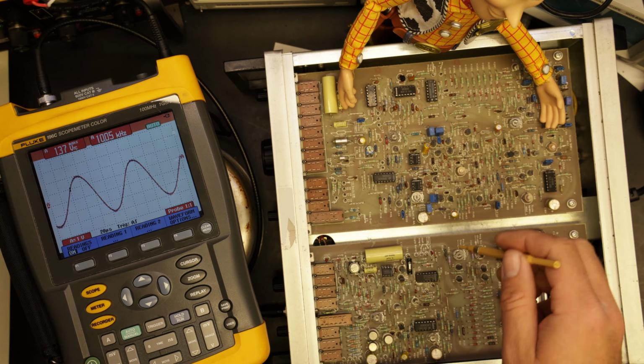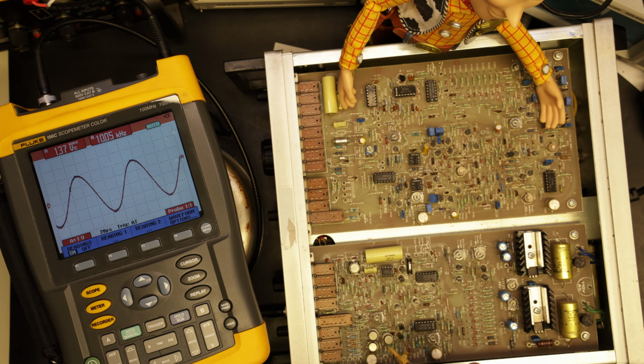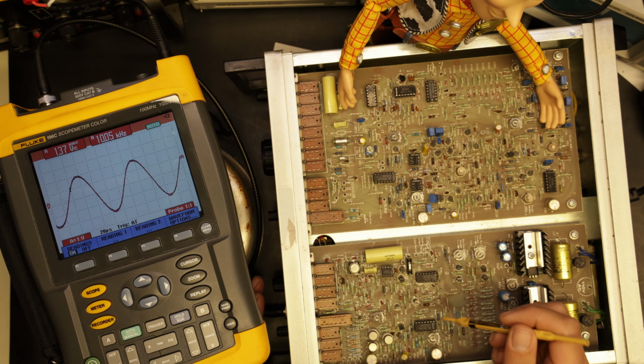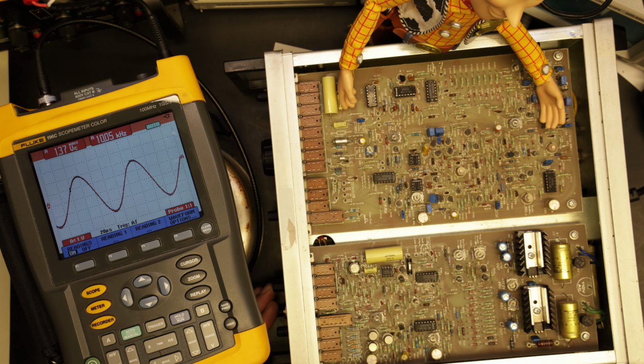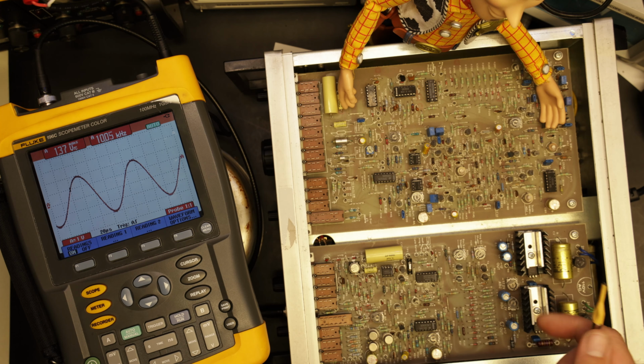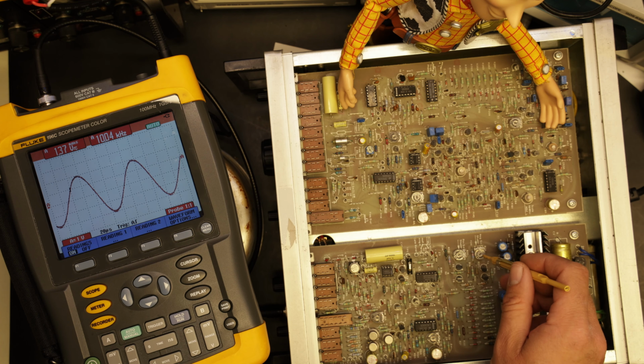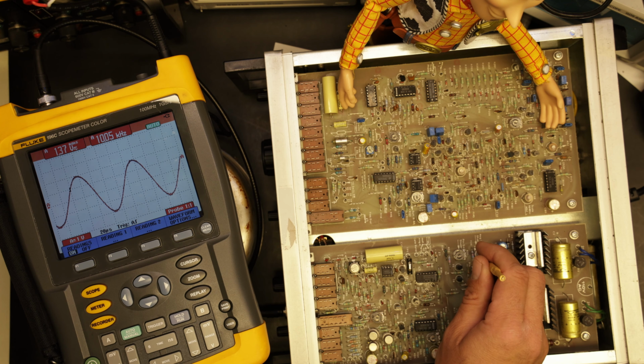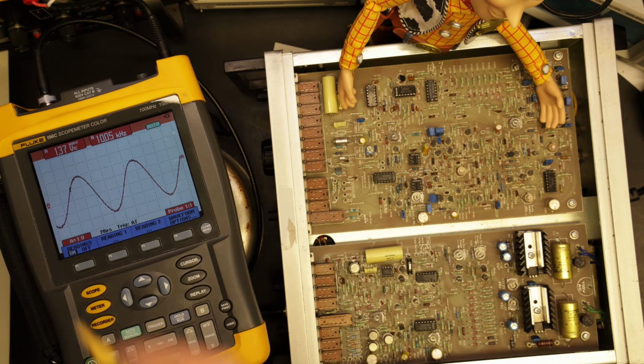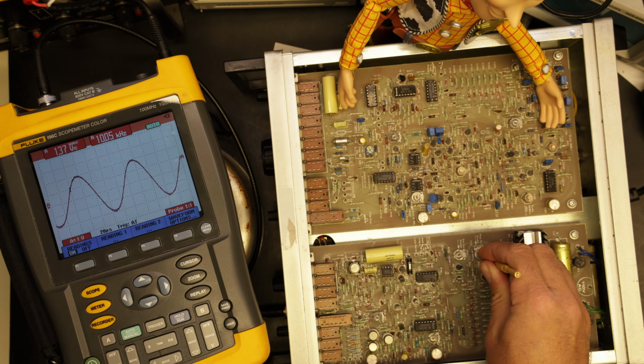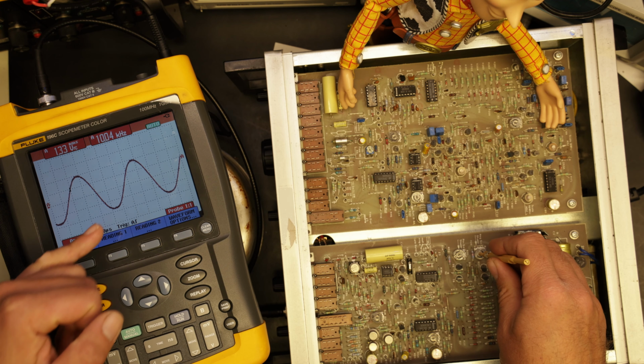So here's the waveform on the auxiliary generator output, and I had set the gain multiplier to 10k, frequency fine adjustment is set to cal, and the sum is set all the way down to the bottom scale. So here you also got the negative and the positive sine shaper. That's for adjusting the waveform, and it looks quite nice where it sits, but I can adjust it so you see what's happening. So this is the negative adjustment.